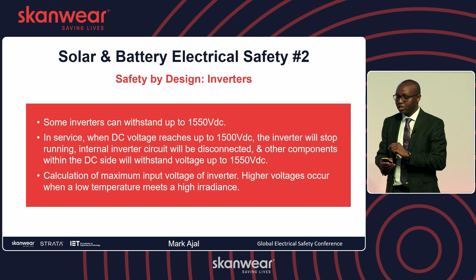Then the selection of materials: low smoke, halogen-free cables. That's what we use, the H1Z2Z2-K for PV strings, and it's 4 square mm, 6 square mm or higher. And then the connectors. Since you can't switch off the primary energy source, which is the sun, you deal with insulating into the conversion side, which is where your MC4 connectors come in and don't allow you to come into physical contact with live sections of the system. Then on the inverters, manufacturers may state the inverter can handle up to 1,550. But in service, safety measures kick in. At 1,500 volts, the inverter stops running. The internal circuit breaker disconnects. And other DC components, like Joseph mentioned, if there's a potential of an overcharge from built-up charges, they'll handle up to that 1,550, but you're not operating the unit in the high voltage DC region.